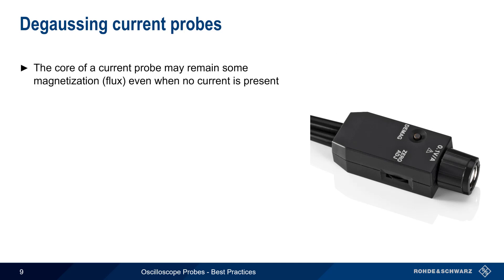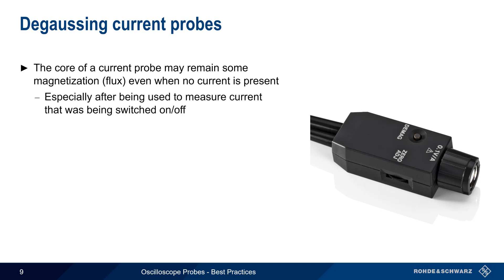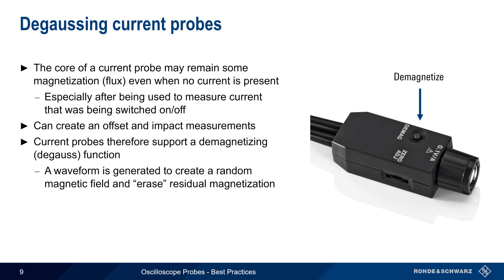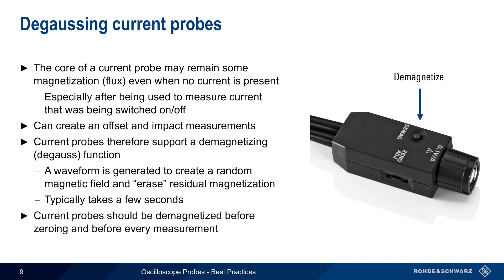The ferromagnetic core of a current probe may retain some magnetism or flux, even when there is no current present. This is not uncommon after a probe has been used to measure a current that was being switched on and off. This residual magnetism can lead to the creation of an offset and impact measurement results. Most current probes therefore support a demagnetizing or degauss function that can be launched either from the probe itself or via the scope's user interface. A special waveform is generated that creates an essentially random magnetic field, erasing any residual magnetism in the probe. This is normally a very quick process that only takes a few seconds. Whenever using current probes, it's a good idea to degauss the probe both before zeroing as well as before making measurements.